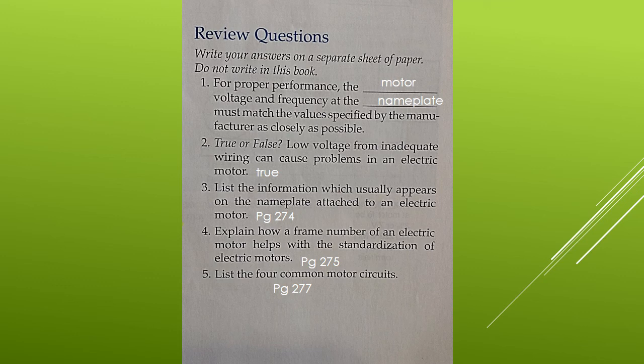Question four, explain how the frame number of an electric motor helps with the standardization of electric motors. And that is, motors of a given horsepower rating are built in a certain size of frame or housing. For standardization, NEMA has assigned a frame number to the frame size for each integral horsepower motor. This ensures that the shaft heights and the dimensions are consistent for motors that are assigned a specific frame number.